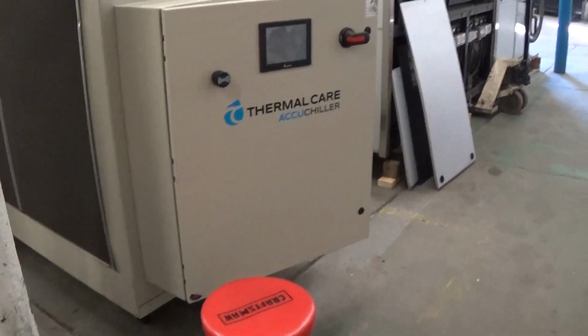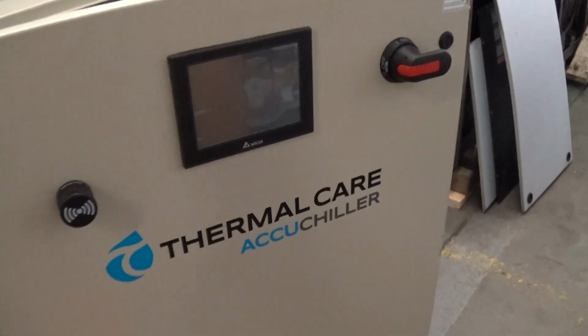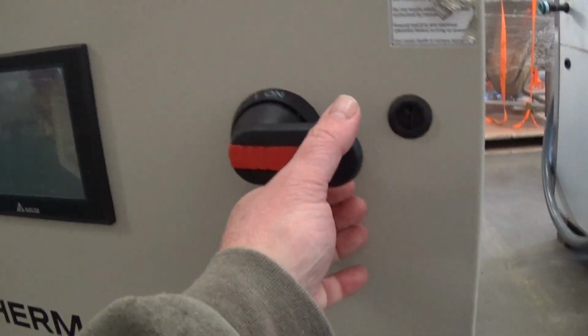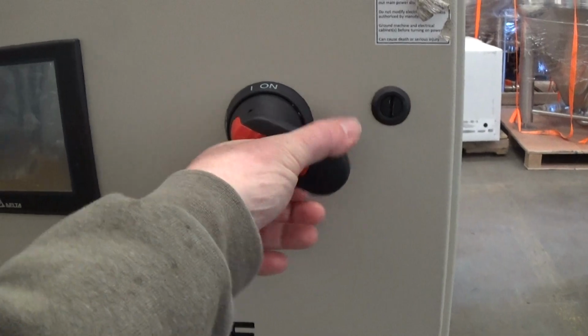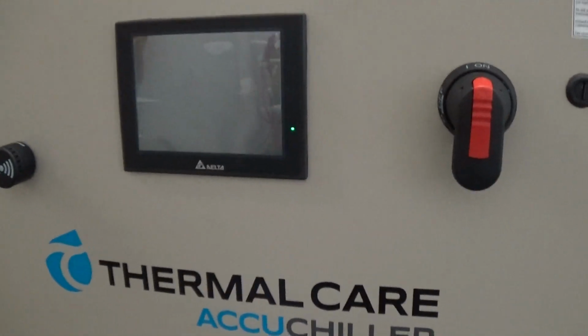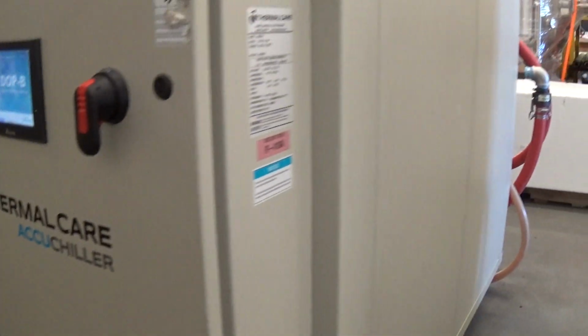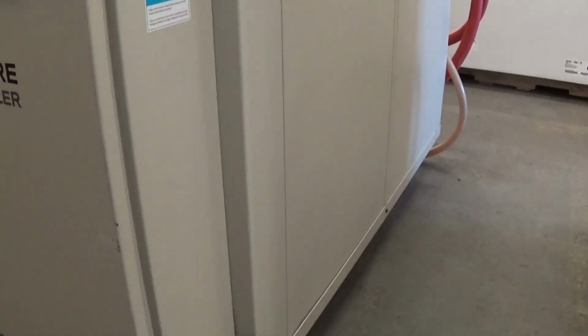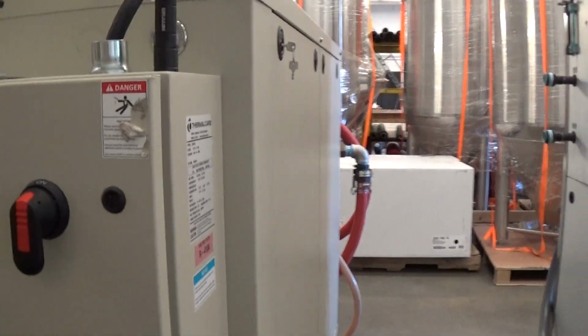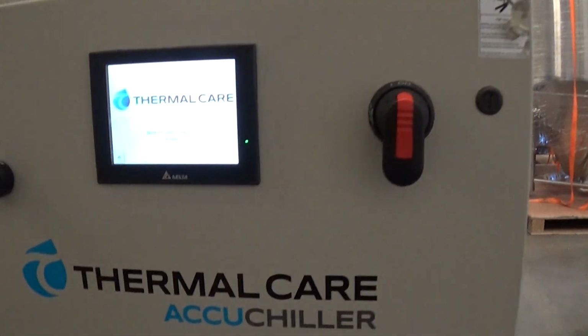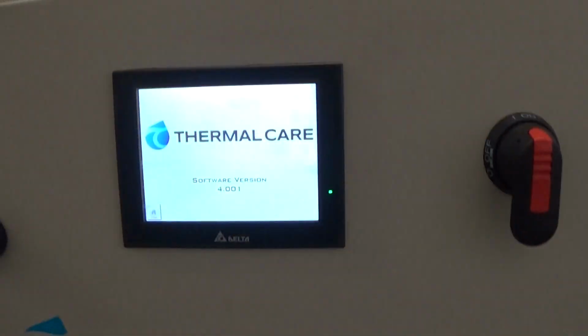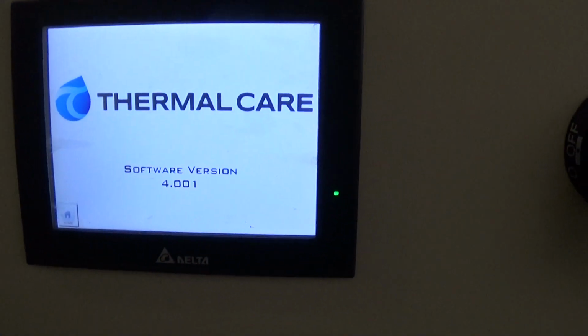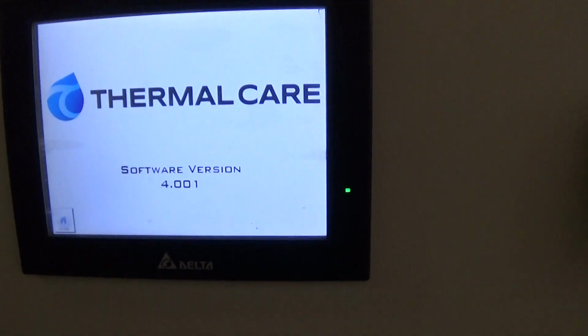This is our video number 2 for this Thermal Care 10-ton inverter variable speed chiller. Just gonna close the cabinet and get her going. We did put the side covers on. You do need the side covers on when you run the unit, otherwise you'll go into a high pressure refrigerant alarm because you're not getting enough airflow through the condenser coils.